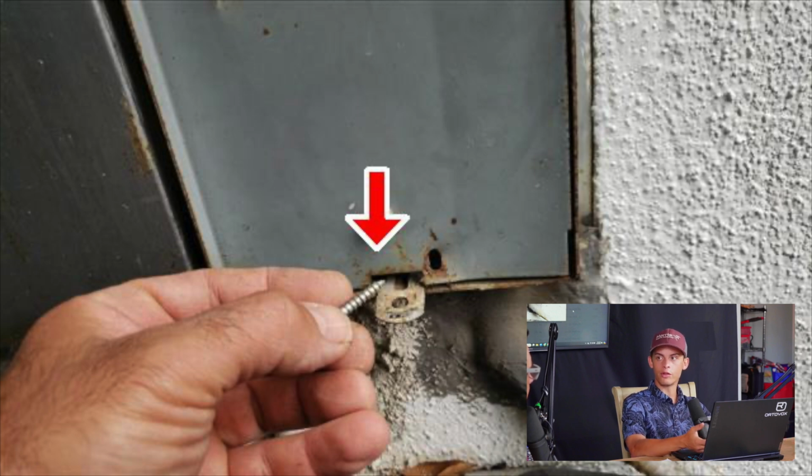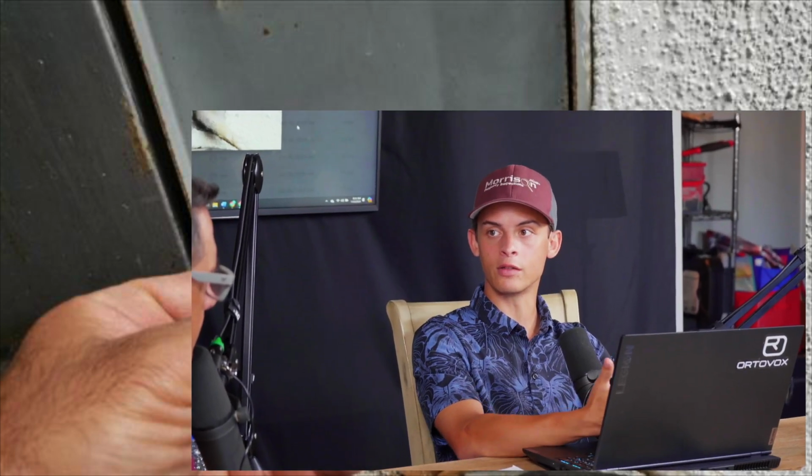Right. You don't know if it's pierced a wire. Right. You don't know if it's pointy. This is actually not allowed for the reason that this screw could be puncturing insulation on high voltage electrical wiring and could be unsafe for the inspector to unscrew or anybody. Yeah. Well, I mean, you're pulling out a screw that's an inch long. There's wiring back there. It's high voltage wiring. It should be a short, blunt tip, and it should be a machine screw. Yep. So we see this all the time. It's egregious. And I've unscrewed at least 2 screws that punctured wiring. Oh yeah, all the time.